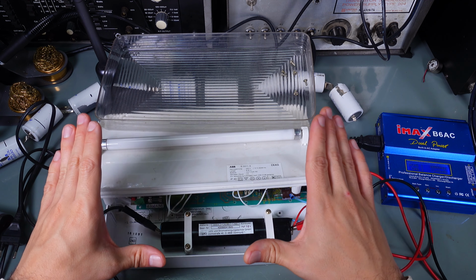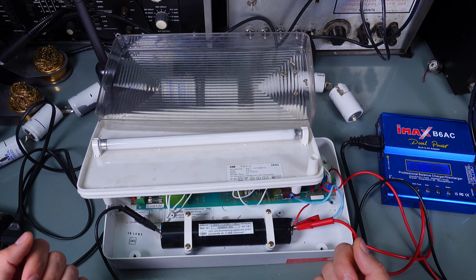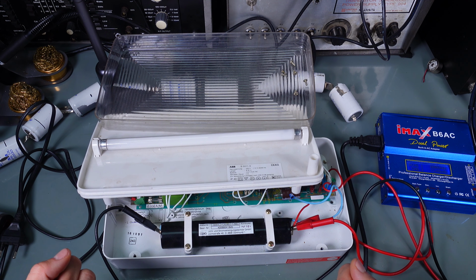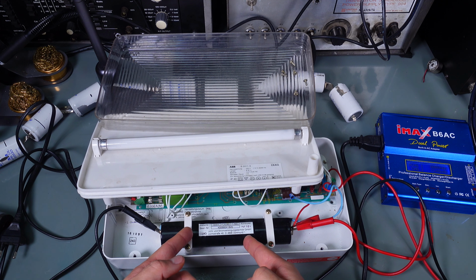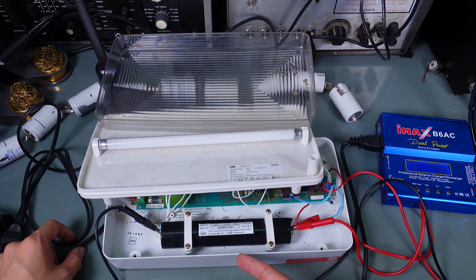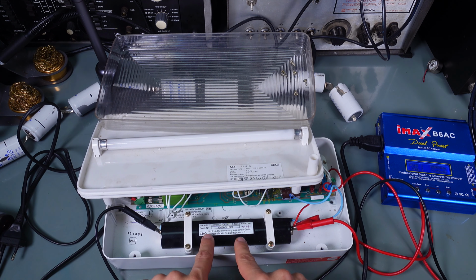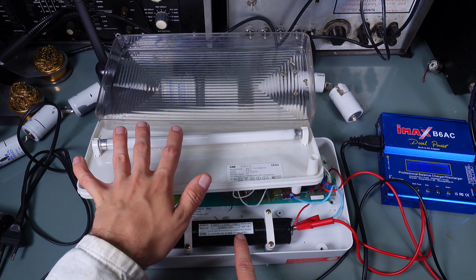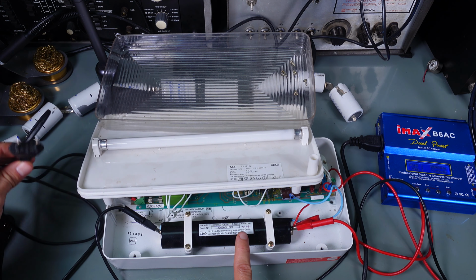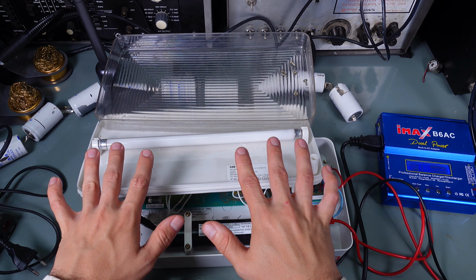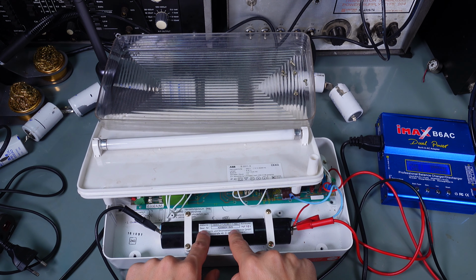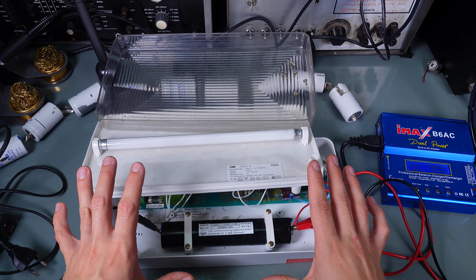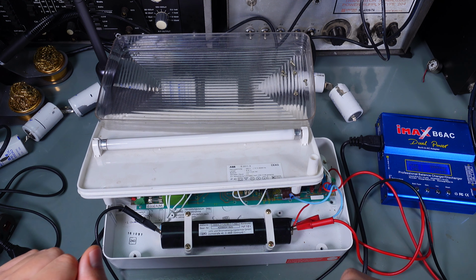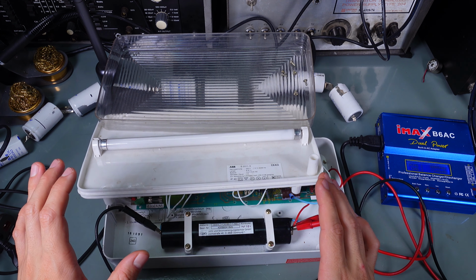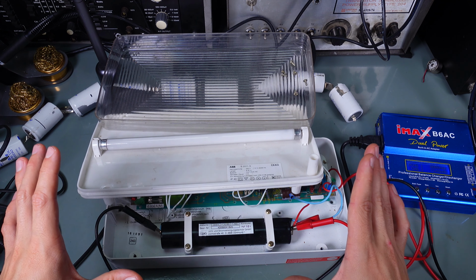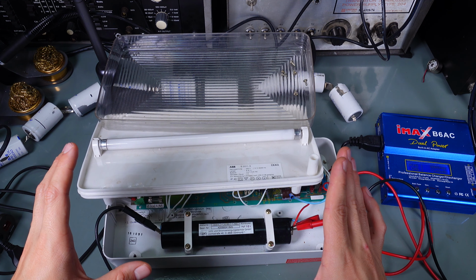First, we need to understand what we are dealing with. This is an emergency light fixture. We've got a battery and AC input, and the AC is recharging that battery. The CFL is not lit normally, but in case of power loss, the CFL is lit from the battery. This system is fully contained, which is great if you've got a public building. I believe they are required by law.